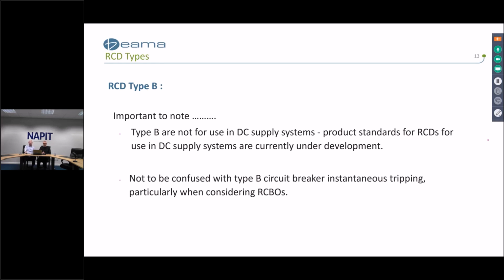And a couple of other important points to note with respect to Type B RCDs. There is sometimes a misconception. Type B, although they are for detecting DC fault currents, are not for use in DC supply systems. That's actually very important to note. It's DC fault currents they can detect, not for use in DC supply systems. So they are for use only in AC supply systems. Product standards for RCDs for use in DC supply systems are currently under development, but are not yet available.